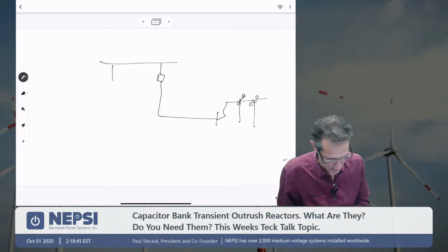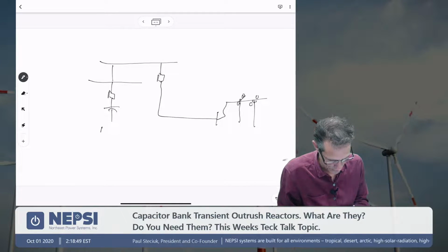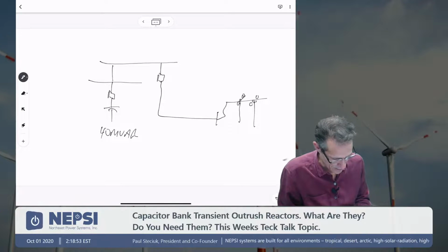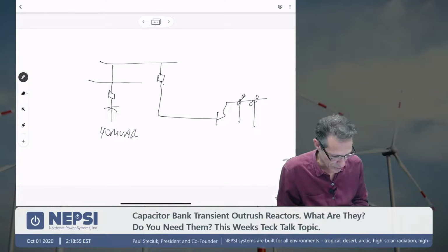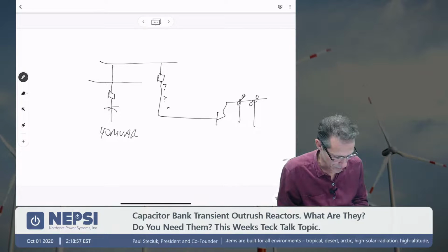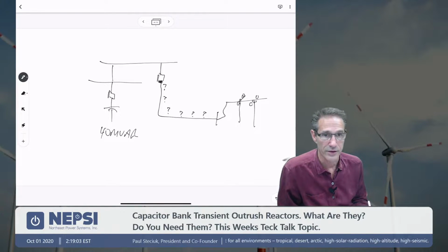The cap bank being here. So you have some large cap bank here, say 40 MVAR. And if there's a fault, the question becomes, where can we have a fault? Where is the logical location to have a fault? Certainly you could have one inside the switchgear there.